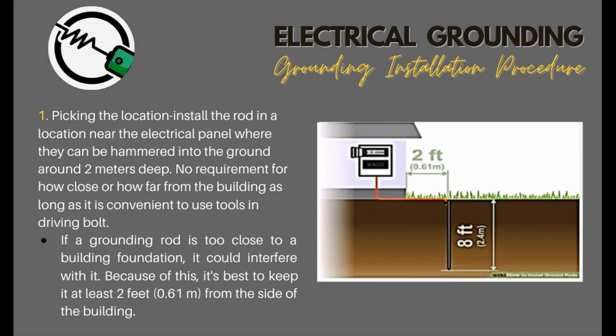Grounding installation procedure. 1. Picking the location. Install the rod in a location near the electrical panel where they can be hammered into the ground around 2 meters deep. No requirement for how close or how far from the building as long as it is convenient to use tools in driving bolt. If a grounding rod is too close to a building foundation, it could interfere with it. Because of this, it's best to keep it at least 2 feet, 0.61 meters, from the side of the building.